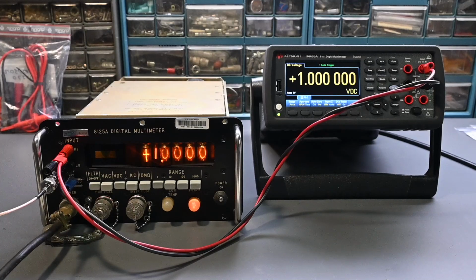Now, the only thing that I couldn't do that's listed in the calibration procedure is to verify the accuracy up to 1,000 volts AC at up to 20 kilohertz, because I just don't have a power supply that has that capability. But I was able to measure up to several hundred volts on the 1,000 volt range at up to 10 kilohertz, and the multimeter worked perfectly fine. Now, in the volts DC range, I was able to measure up to 1,000 volts with no problems.